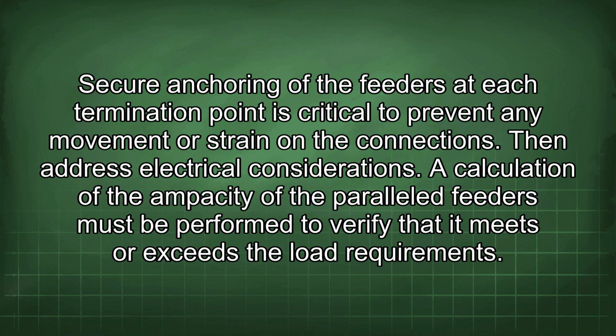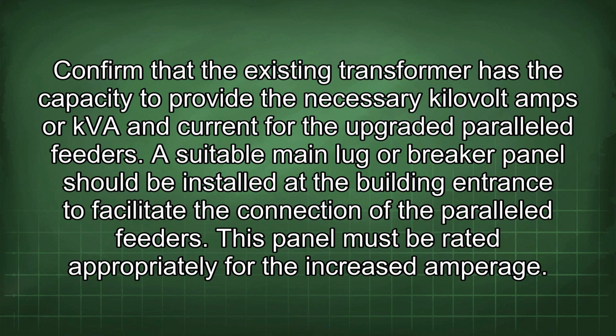Calculation of the ampacity of the parallel feeders must be performed to verify that it meets or exceeds the load requirements. Confirm that the existing transformer has the capacity to provide the necessary kilovolt-amps, or kVA, and current for the upgraded parallel feeders. A suitable main lug or breaker panel should be installed at the building entrance to facilitate the connection of the parallel feeders. This panel must be rated appropriately for the increased amperage.